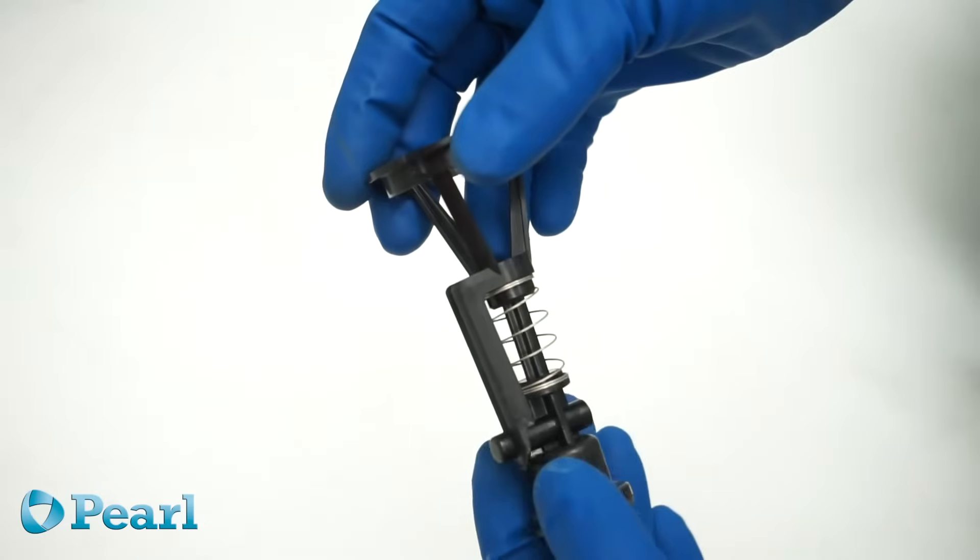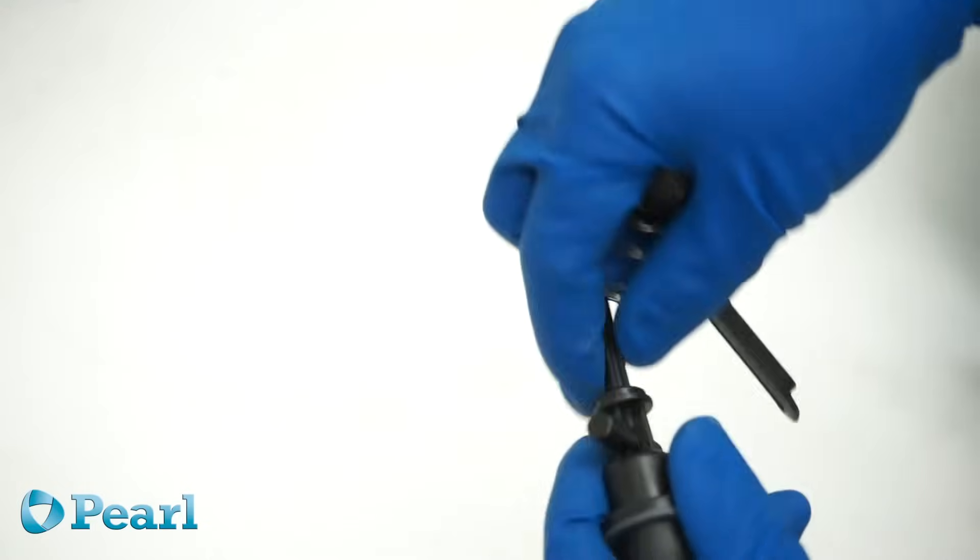The valve should move freely. Take the pieces apart and look for debris and sediments. Clean all the parts including the spring, the guide, and the valve.